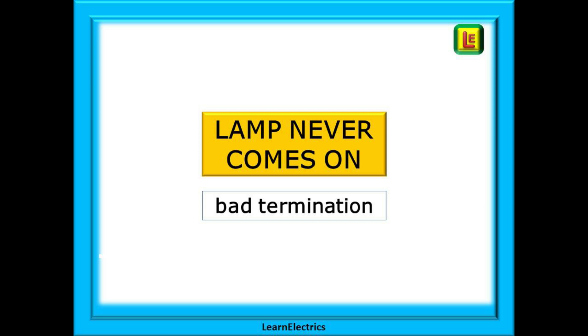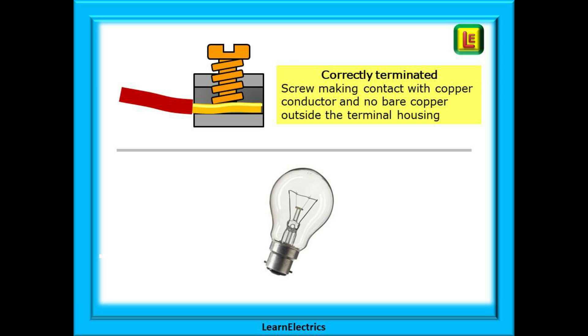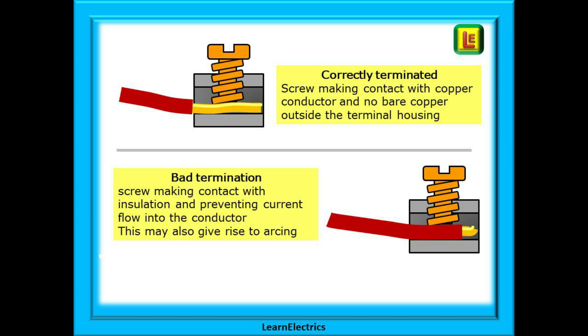Another example of the lamp never coming on is the result of bad terminations. Here is a correctly terminated conductor in a cutaway view of a terminal — the screw is firmly clamping the copper against the metal of the terminal. And here is an example of a bad termination, common after DIY work and an easy fault to simulate for an assessment. The screw is trapping the PVC insulation against the terminal. The insulation is doing exactly what it is designed to do — it is insulating the copper from the terminal and preventing current flow. An added danger of this fault is that arcing and sparking may result if the copper is close to but not touching the terminal, and this situation could give rise to fires.